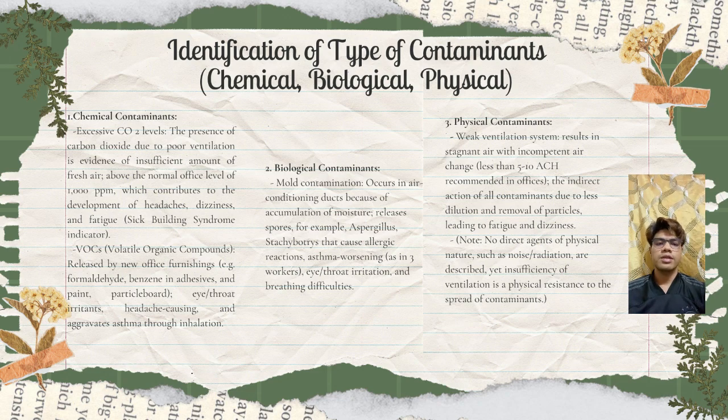Chemical contaminants: excessive carbon dioxide CO2 levels above 1,000 parts per million indicate insufficient fresh air supply due to poor ventilation. This contributes to headaches, dizziness, and fatigue, which are common indicators of sick building syndrome.